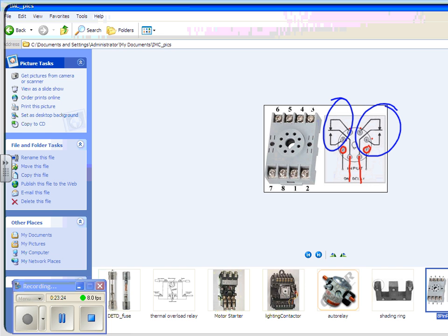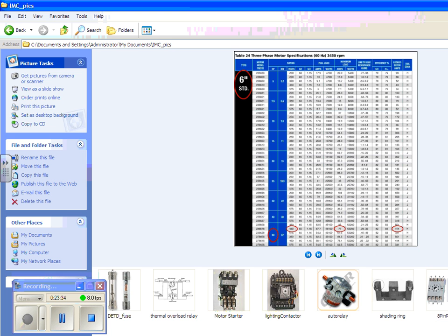Let me stop this for a second. All right, so now we're going to talk about motor starters. And we're going to talk about sizing motor starters. And motor starters are sized by the horsepower of the motor you're starting, primarily by the horsepower. Now there are 2 kinds, NEMA and IEC. NEMA stands for National Electrical Manufacturers Association, and IEC is an acronym for International Electrotechnical Commission.